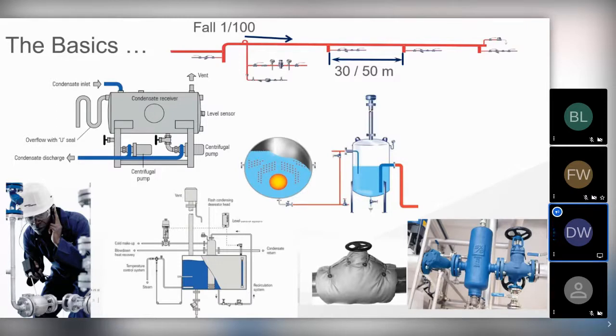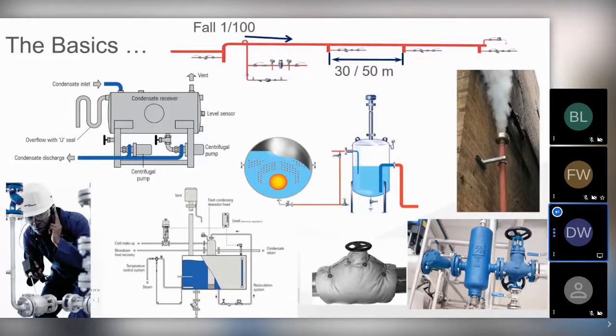But ultimately, we want to do everything we can to minimize any venting steam. That could be either from flash steam, or it could be from any steam traps that have failed in the open position. We want to do everything we can, first of all, to minimize or eliminate those losses, or further still, look at different ways in which that heat energy can be utilized.